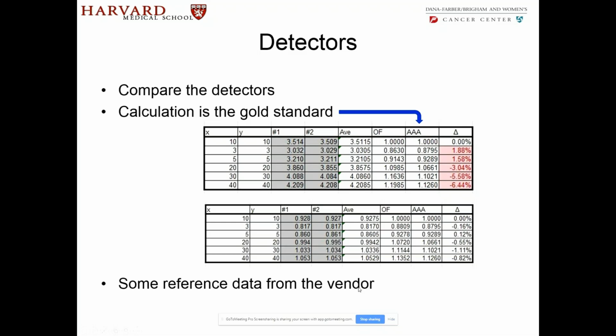Some reference data is obtained or given by the vendors. They don't necessarily give it out for TrueBeams. For TX machines, they used to. They call it the golden beam data. That's another way of doing a cross-check of what your outputs are. A good reason for doing it and not just accepting what the vendor has given to you is that tomorrow when you do your annual, you want to check your machine, and it's always good to have your own reference data. If you don't have your own reference data, then you don't know if the machine has changed over time. You may keep looking at the golden beam data, but it's hard to say if there's a particular change that happened after maybe some repair was done.